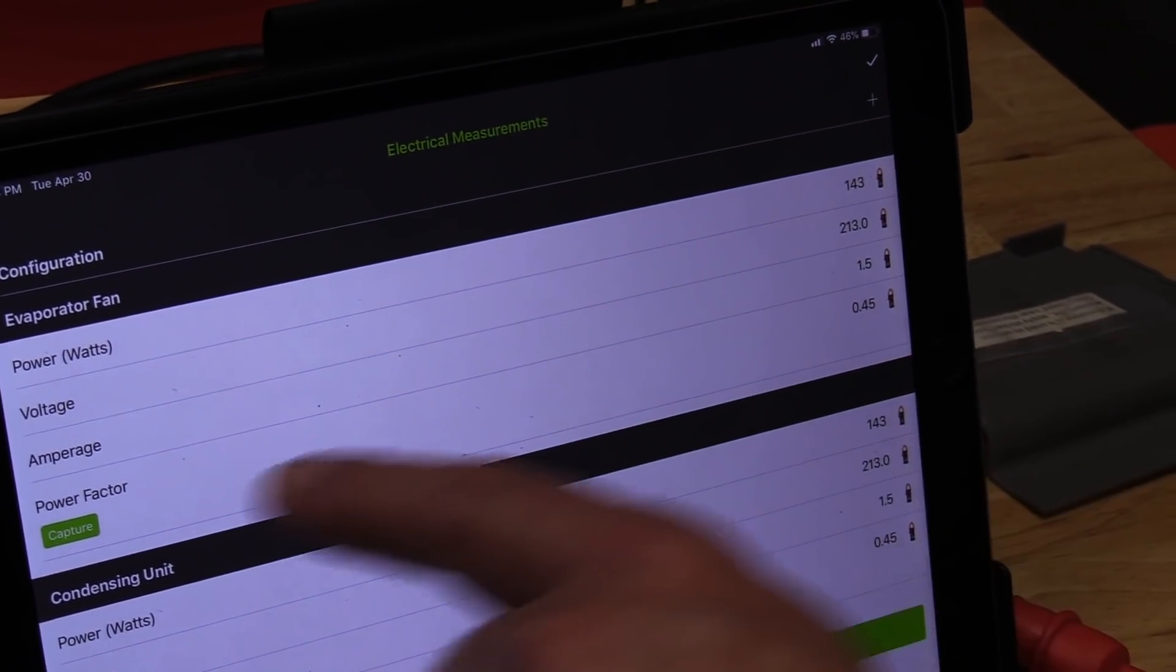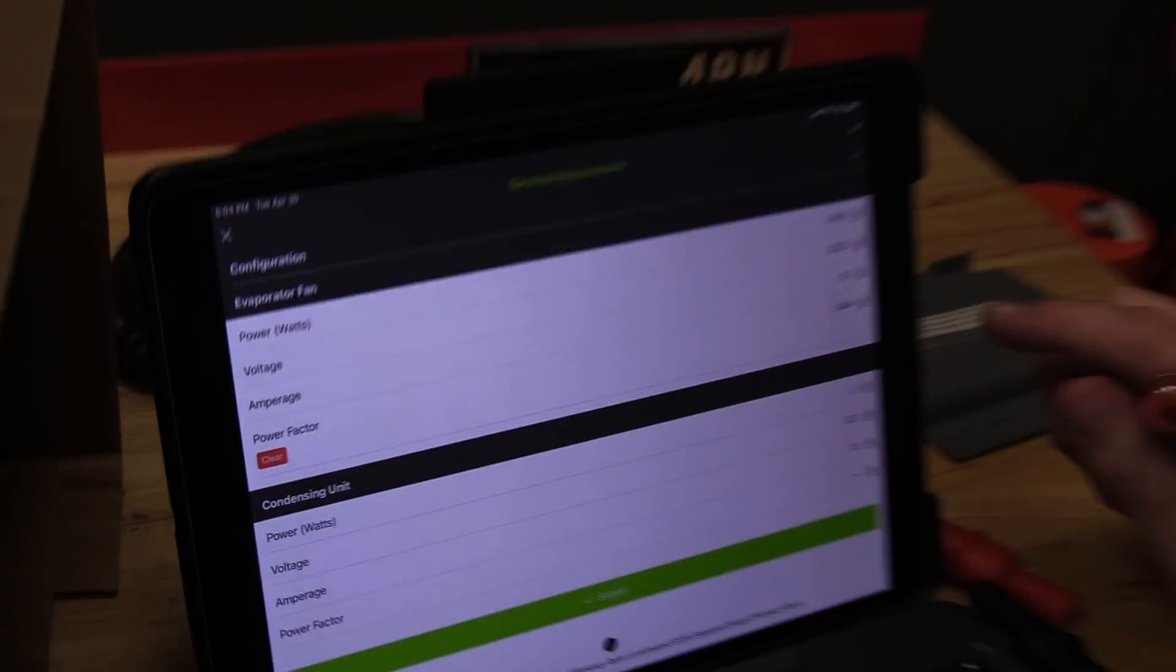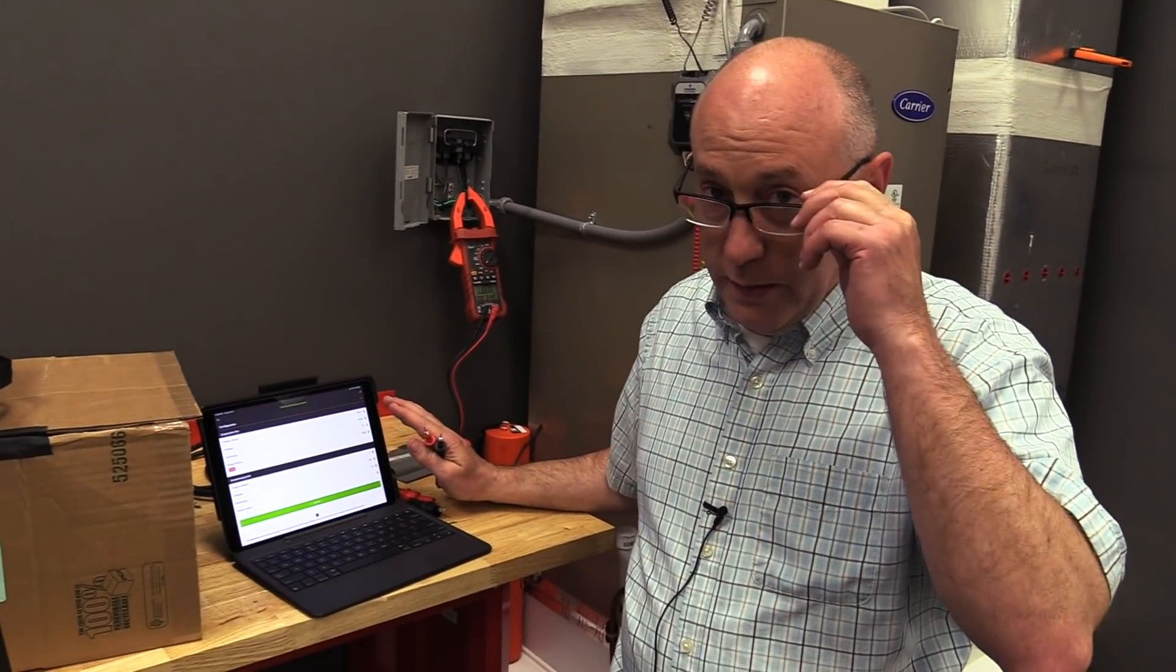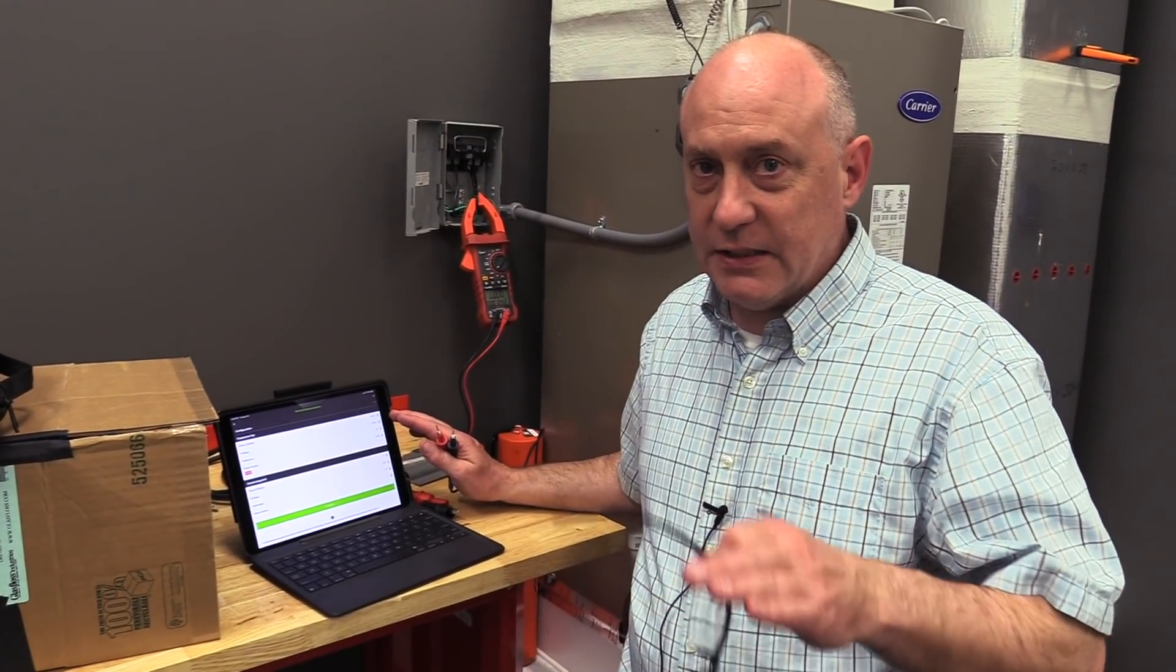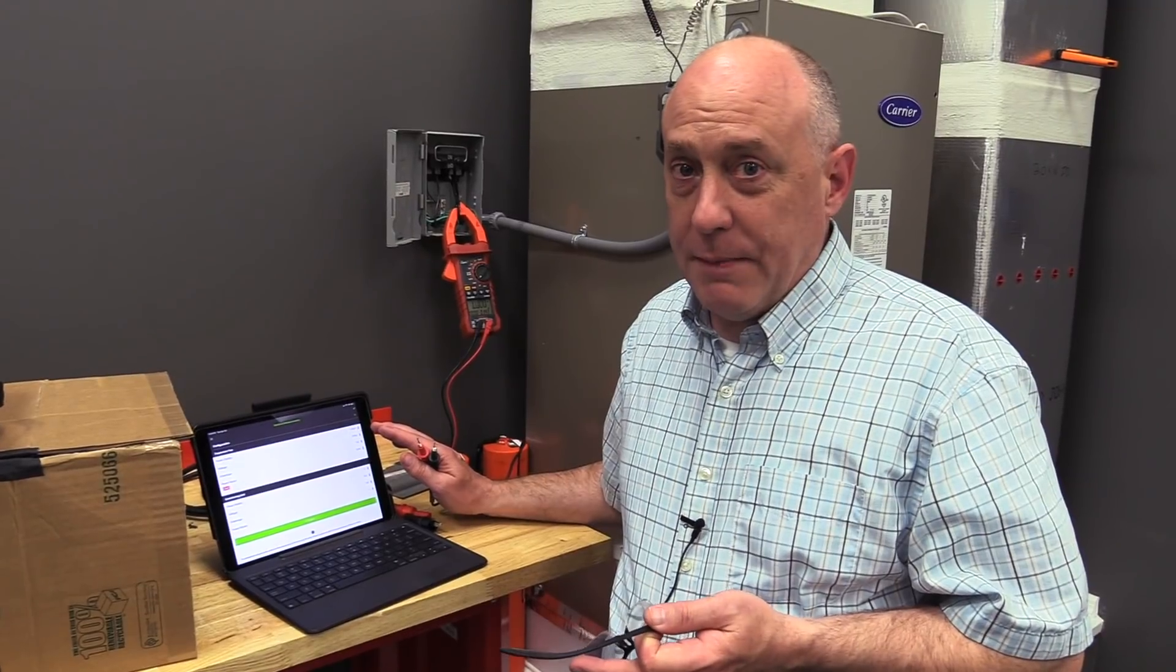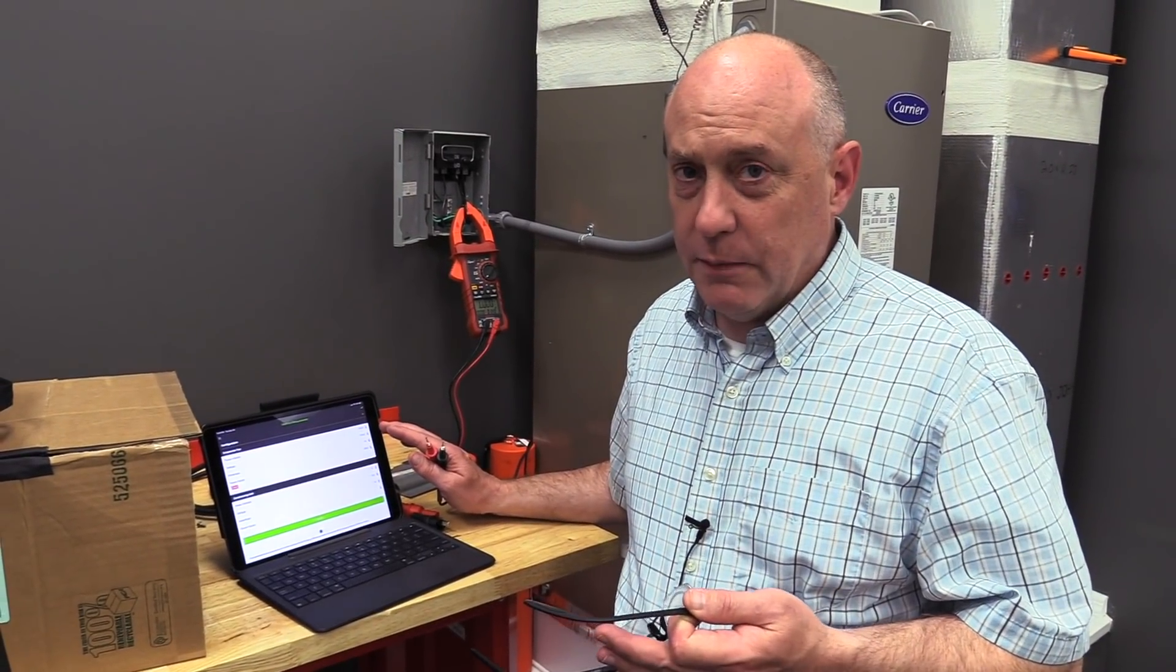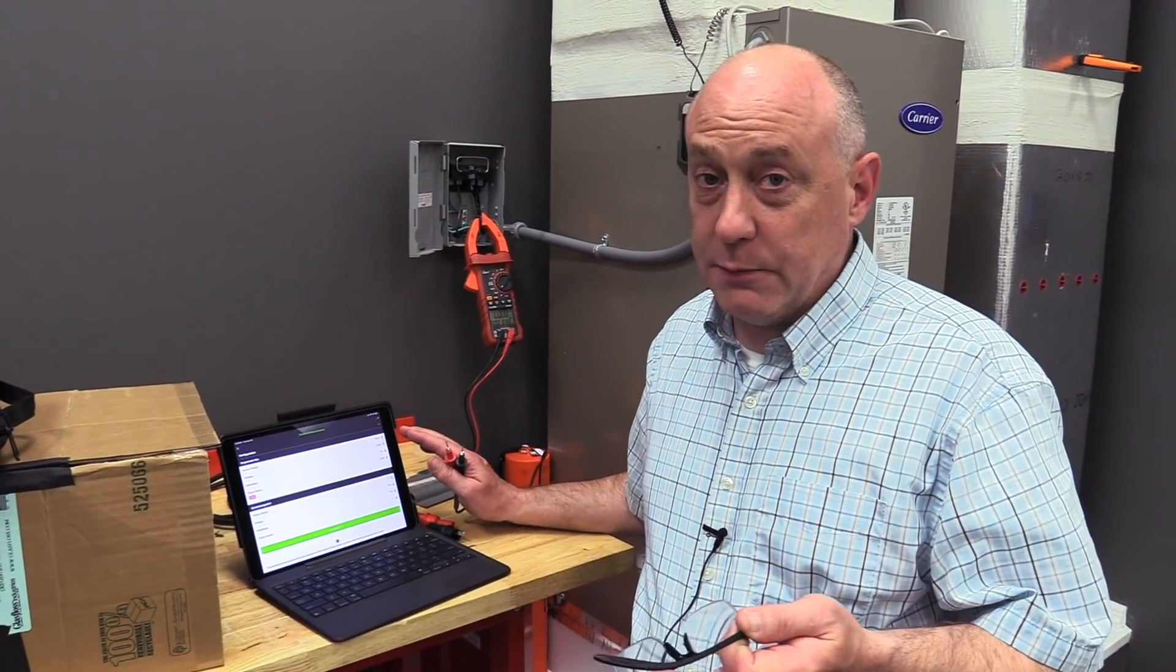Now this is an ECM motor, and low power factor with an ECM is nothing to be worried about. They actually pulsate; they don't fully use the AC sine wave. So what you'll see is what looks like a low power factor that might be a problem, but in fact it's just the way the technology works—it's a pulsating DC. This is perfectly fine and part of the reason ECMs save energy, so that low power factor is not an issue.